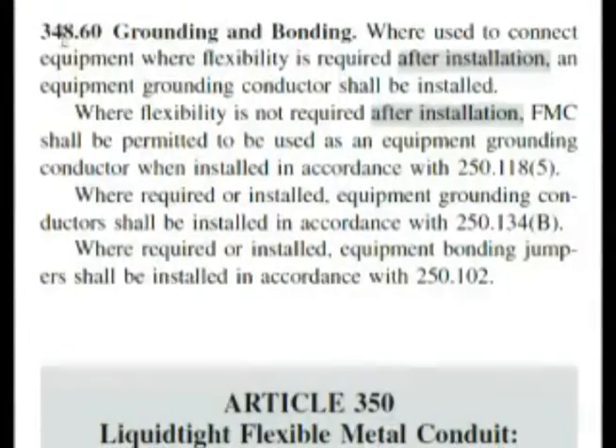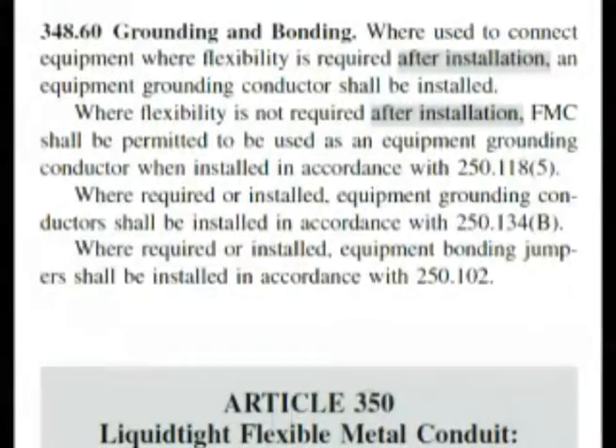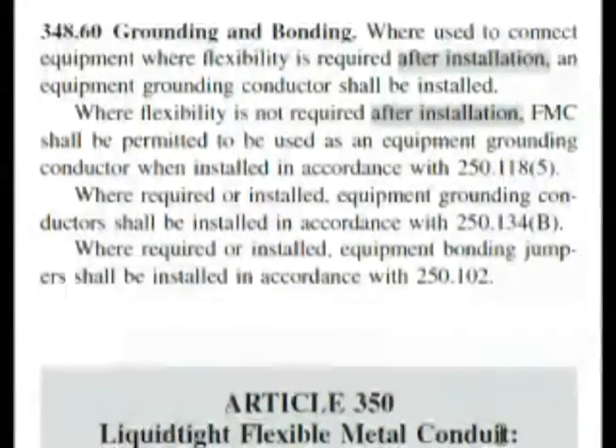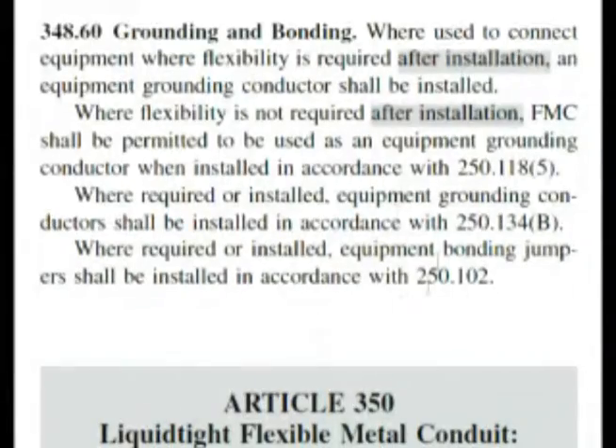Here we are at 348.60. Now look down here — article 350, and it's liquidtight flexible metal conduit, type LFMC, and you can read it on your page when you're following in your book. But this is the very last thing on FMC. And if we read it, this first paragraph is almost word for word: 'Where used to connect equipment where flexibility is required after installation, an equipment grounding conductor shall be installed.' And that is answer A.